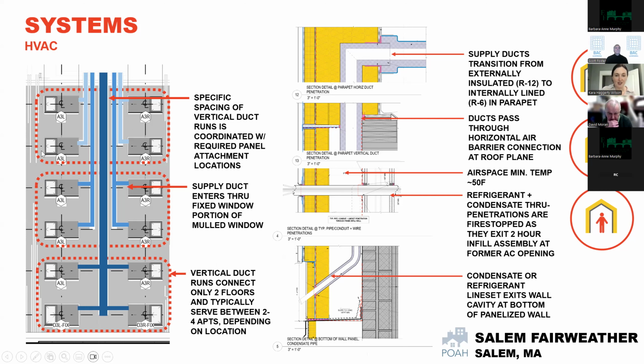We're routing into the jambs, and I have a detail on the next sheet. This wall section shows the roof at the top, with roof ductwork transitioning into the parapet, which is site built. Once we get to about the existing roof line is where the panels really start, as far as top of panel. We've got a 2-hour infill at the former air conditioning sleeve, creating fire stopping situations for our condensate and refrigerant lines. At the bottom of the building, we're sitting these panels on a concrete curb, site built around the perimeter, with our condensate and refrigerant line sets exiting out through the bottom.